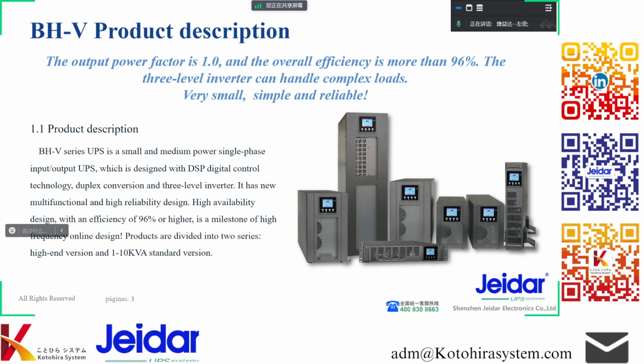High availability design with an efficiency of 96% or higher is a milestone of high frequency online design. Products are divided into series, high-end version, and 1 to 10 kVA standard version. High-frequency machines on the market now are basically two-level or three-level half bridges. Our products have a three-level full bridge architecture and are very impact resistant, so they are efficient and stable.